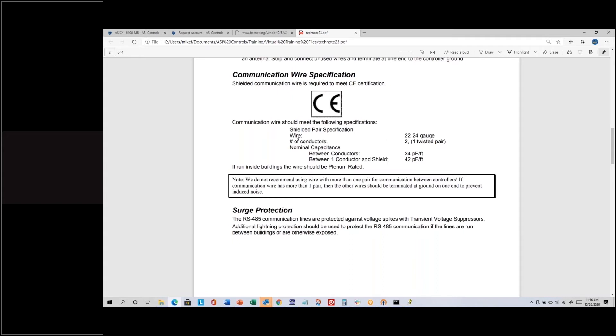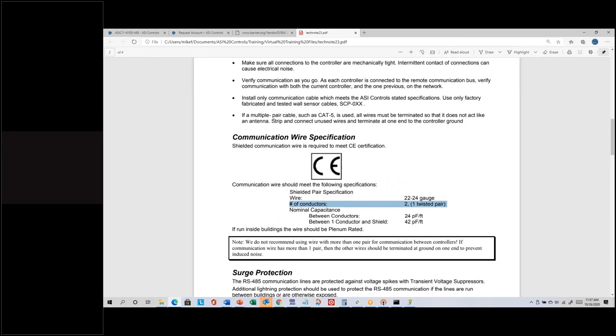Here is the communication wire specification. On whatever communication wire you're using, make sure it meets our specification. Wire gauge — I don't think is critically important, but our RS-485 terminal block can accommodate a pair of 18-gauge wires. The number of conductors is two, which is one twisted pair — that aligns with the recommendation not to use multiple-pair communication wiring. The twist itself is important: there's a specific number of twists per foot that improves communication reliability compared to thermostat wire with fewer or no twists.